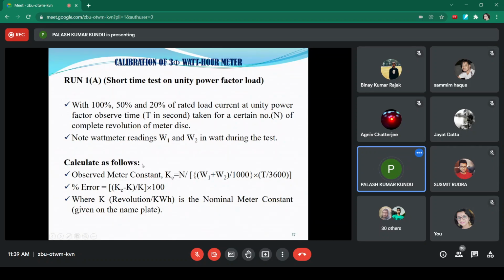So the formula to find the percentage error is this, where Kc is the experimental value of the meter constant, computed from the standard wattmeter reading and the time measured by the stopwatch, and K is the meter constant specified on the nameplate by the manufacturer. So the percentage error according to the formula gives the error caused by the disc rotation, because the meter constant is the least count of the meter due to the disc rotation.